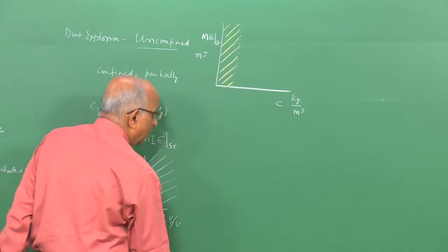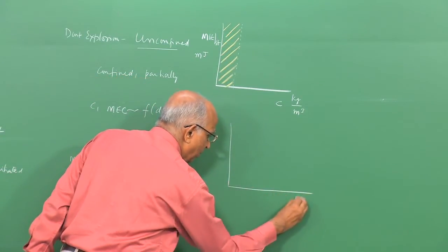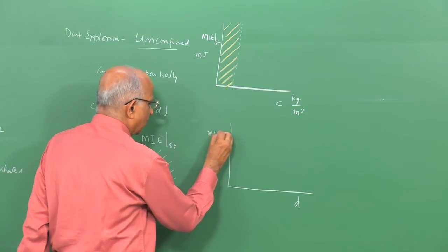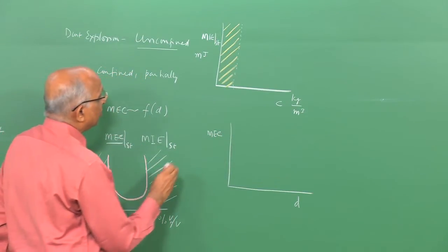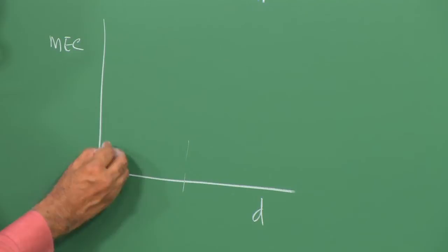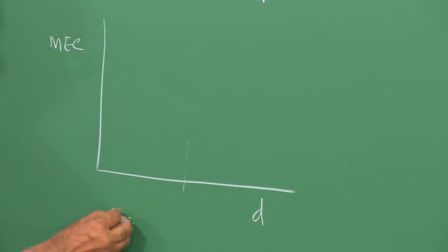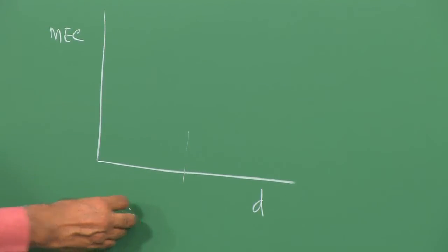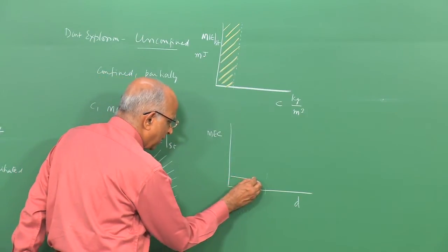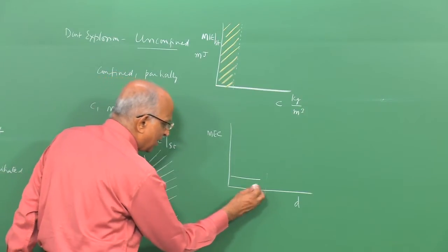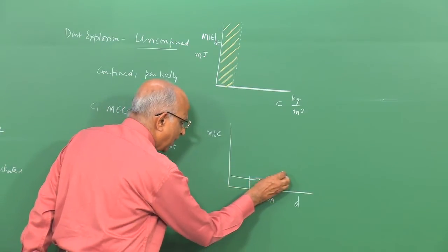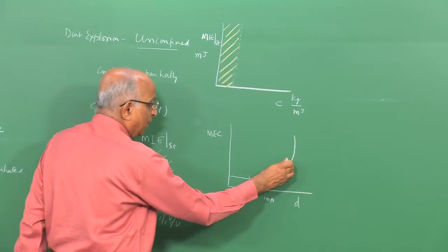How did we come to this? We said, I plot the diameter of the dust particles over here. I plot over here the minimum explosive concentration, MEC, for the dust mixture. And what did we find? If the diameter is quite small, some minimum concentration is required such that a flammable vapor-air mixture can form just at the limits of flammability, and therefore I require some minimum explosive concentration when the diameter is typically less than around 100 micron or so.